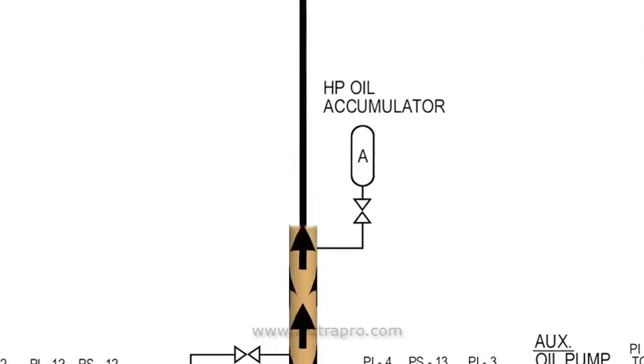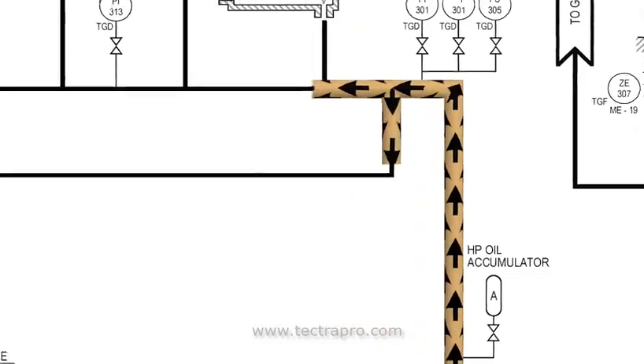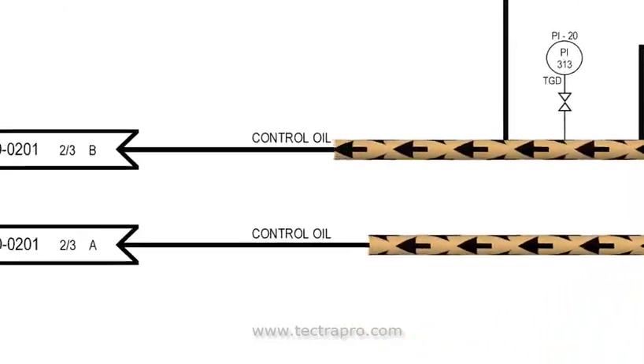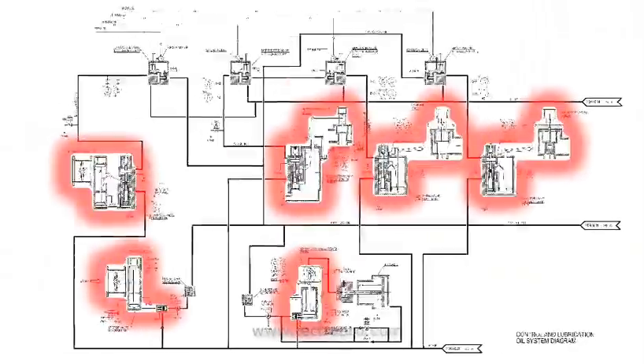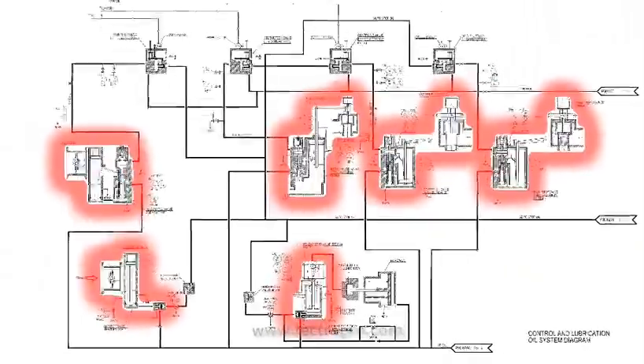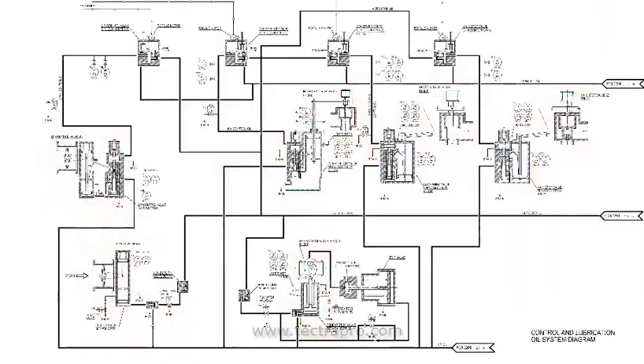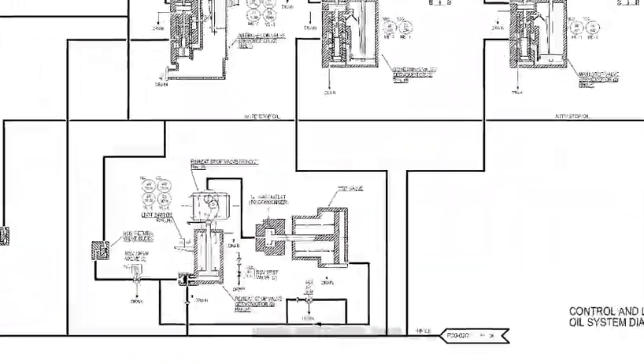High pressure accumulators installed in the transport line help minimize surge in the system. Control oil is used to operate all steam turbine control and stop valves. Control oil also interfaces in turbine supervisory instrumentation.